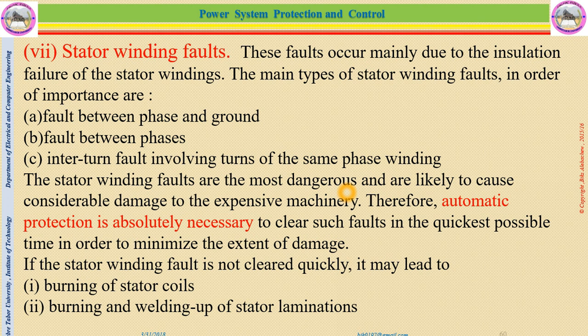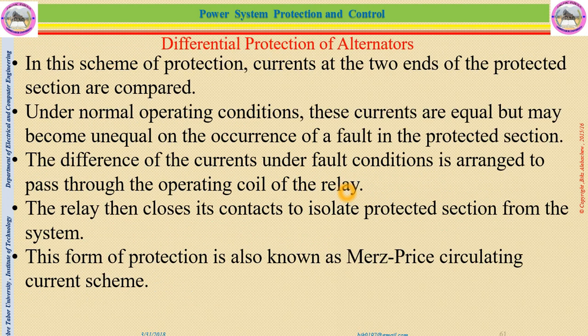So automatic protection is absolutely necessary to clear such faults in the quickest possible time in order to minimize the extent of the damage to the generator as well as the substations. If the stator winding fault is not cleared quickly, it may lead to burning of stator coils. If there is a burning of stator coils, we cannot generate any power, and we can totally lose the generation station. It may also lead to burning and welding up of stator laminations. If the stator lamination is totally damaged, hopefully we can move the generator to another place. So this is a very, very critical issue, and it may suffer from different problems.